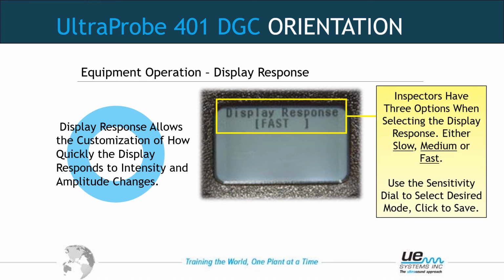We then come to display response. Once you choose display response and enter into here, display response has fast, medium, or slow. Fast is a little too fast. If you're using the intensity meter, it pegs out very fast. Things move around the screen fast. If you're using slow, you wind up double clicking on that sensitivity knob because the screen does not react as fast as you think it should. Medium seems to be about where everybody thinks it should be.